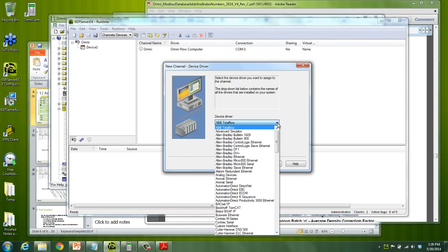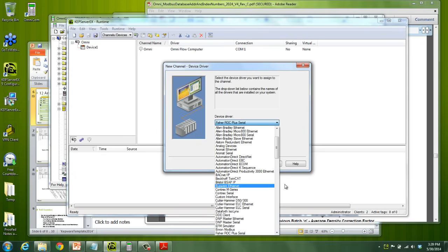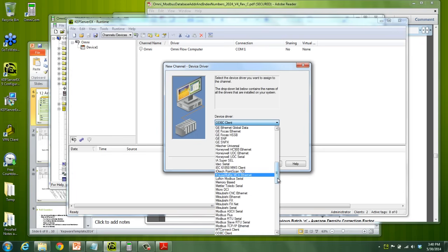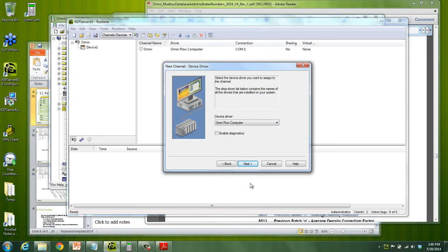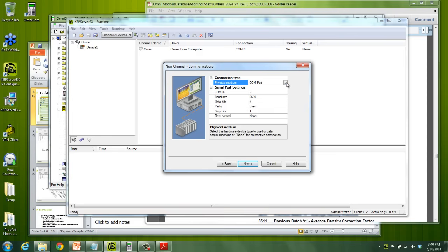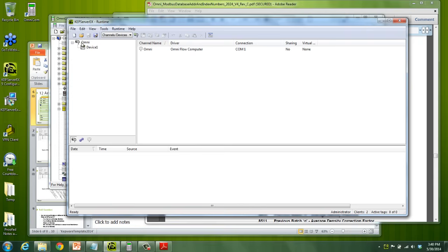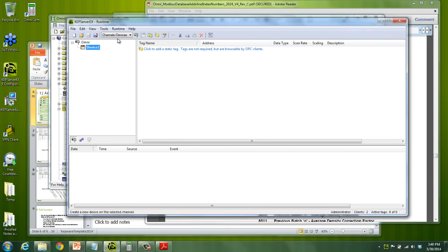So you see on the channel level we have a bunch of different devices and drivers that we support. So we have ABB Total Flow, Bristol, Fisher ROC, and then of course relevant to this webinar we have Omni. So when I created that Omni channel, I selected the OMNI Flow Computer driver, and then here I selected my connection type, whether it's over a COM serial port or Ethernet. So that's what I did to create the channel, and then I went ahead and created a device.